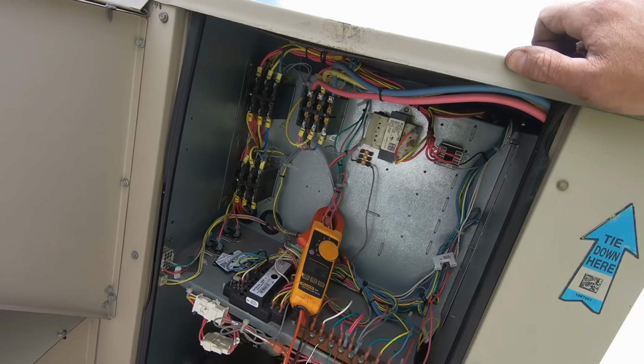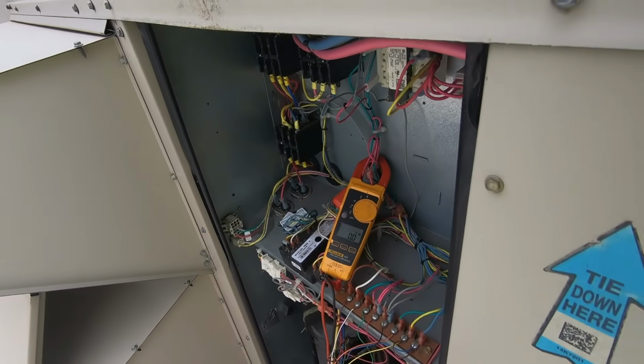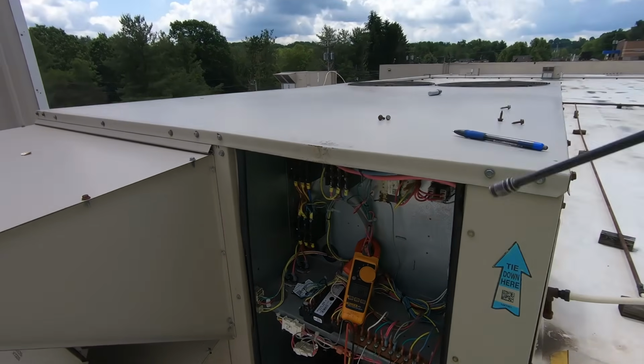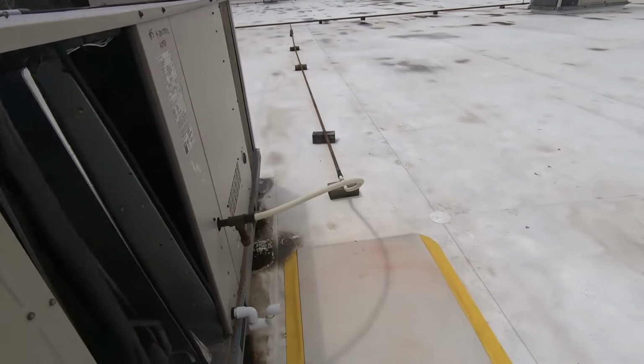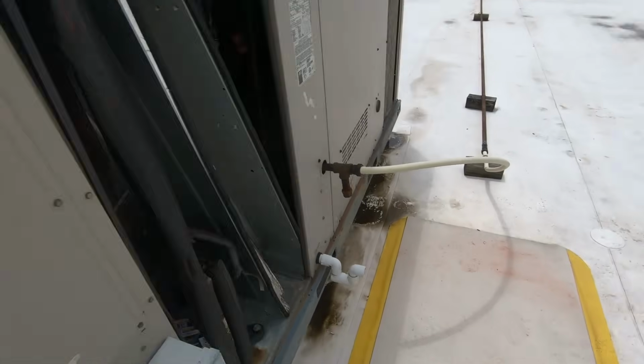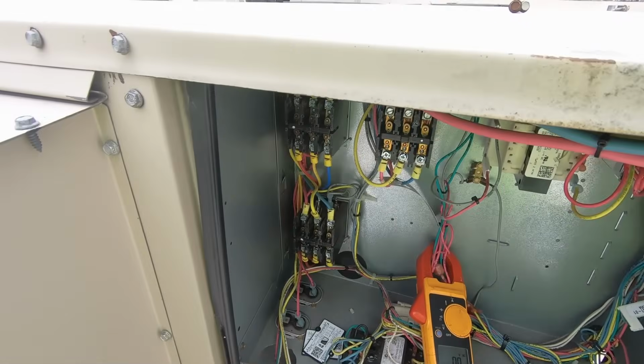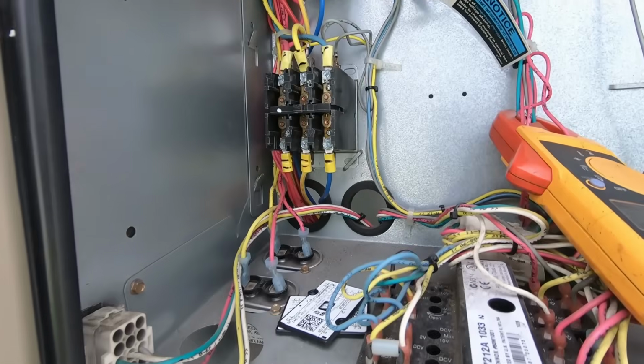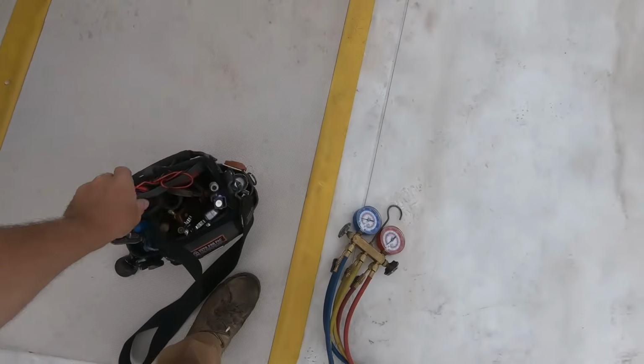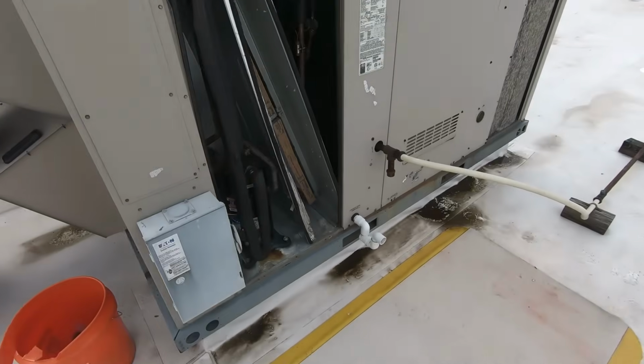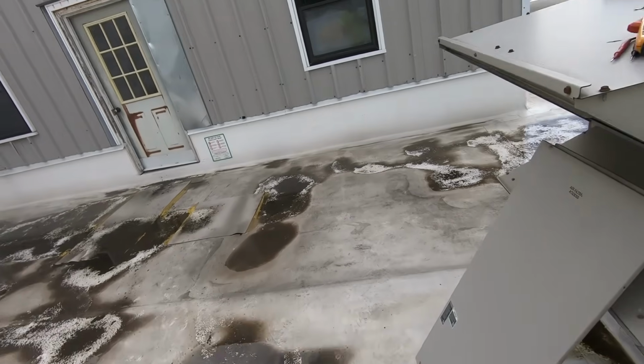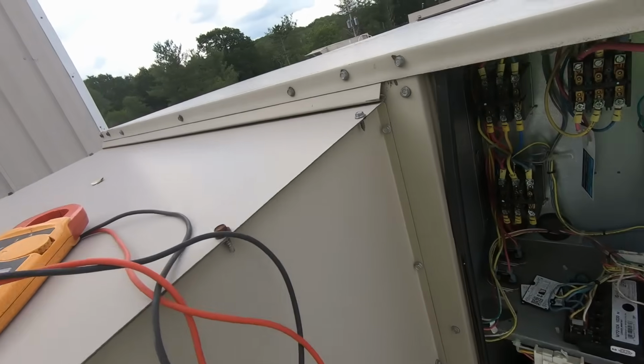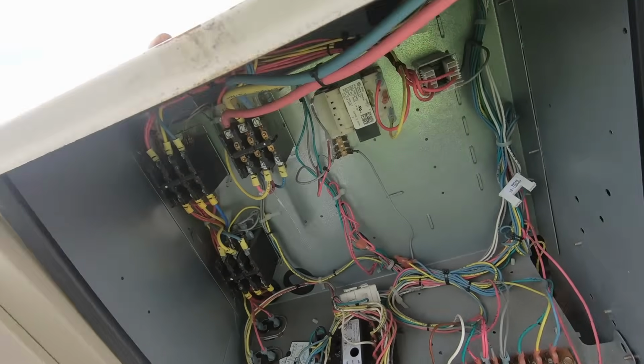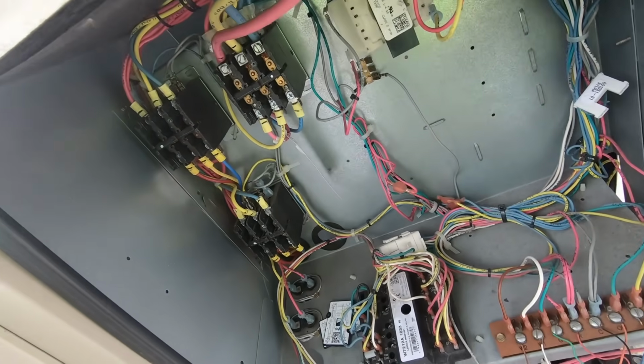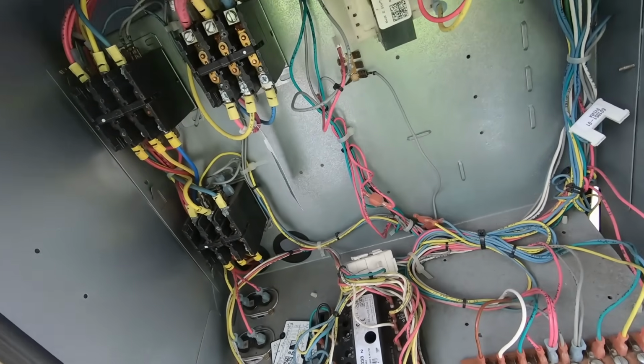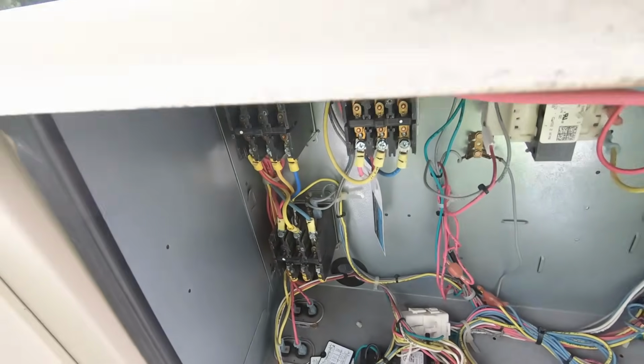Has not tripped. Let's check these contactor coils. That's a good sign. Didn't trip, but maybe when things start to try and kick on, they might. So I'm gonna pull these contactor coil wires, test each coil. All my coils are reading 7.3. I think we're good on the coils. Now, I'm just gonna jump out. Well, Y1 and Y2 are jumped out on here. I'm just gonna jump on cooling.